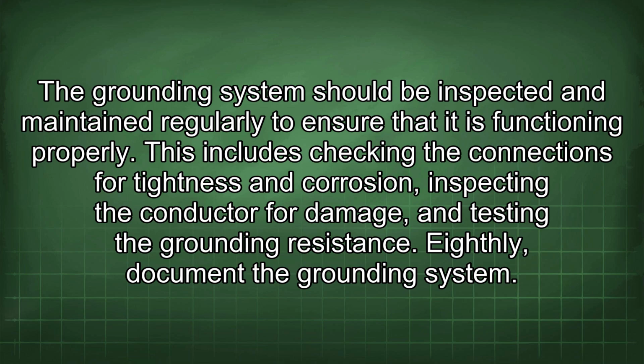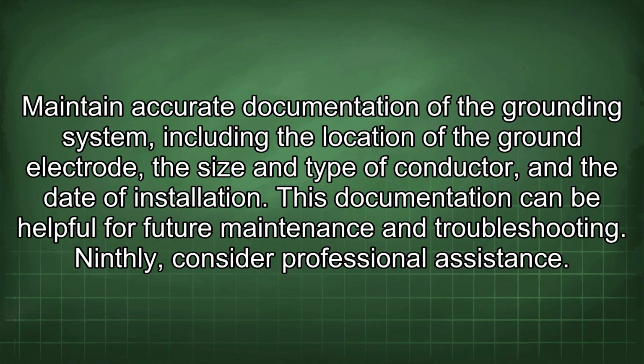This includes checking the connections for tightness and corrosion, inspecting the conductor for damage, and testing the grounding resistance. Eighthly, document the grounding system. Maintain accurate documentation of the grounding system, including the location of the ground electrode, the size and type of conductor, and the date of installation.